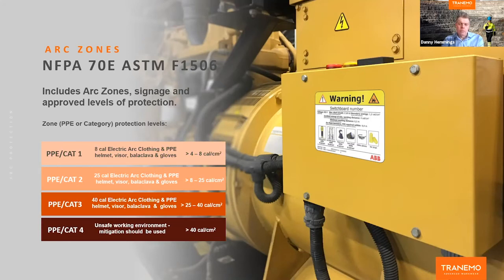One thing we do say to people, and again, sometimes the misinformation in the market, is people will strive to get testing, particularly on layer testing, of higher and higher and higher calorific protection figures. Really, to put it in the real world, no one should be in a working environment where there is a recognized risk of over 40 calories, because that is a huge incident, and it's very remiss of any manufacturer to market solutions at 50, 60, 70 cal, because really that's an incident that no one wants to be involved in, because it will be like a bomb going off. So it's false protection to really take people above that threshold.